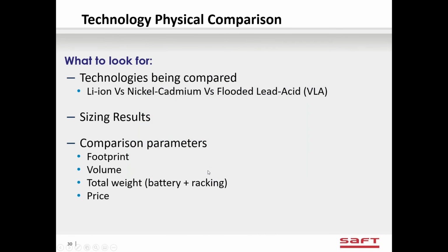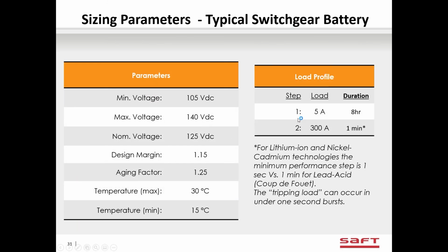This is a switchgear comparison I put together. We're going to look at the footprint, the volume, total weight, and the price. This is a simple profile: 5 amps continuous for 8 hours and 300 amps for 1 minute at the end. 120 volt system. These are some other parameters that we need to know: the maximum temperature and the minimum temperature that the battery would need to run at.